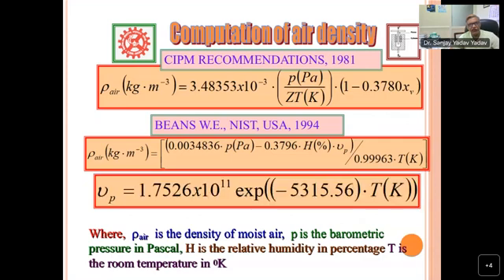So these are the equations for the air density calculation in the calibration room. This is a very, very important equation you can use. This equation is recommended by CIPM in 1981. Some small corrections have been made recently, and this equation is used in NIST by Beans. I have compared both, not much of a difference in the values coming.